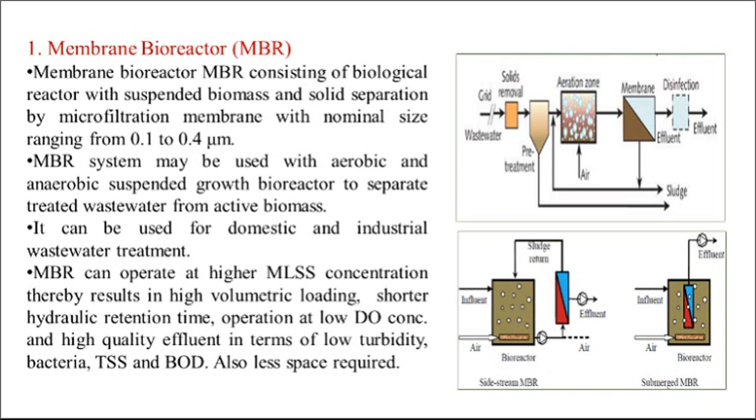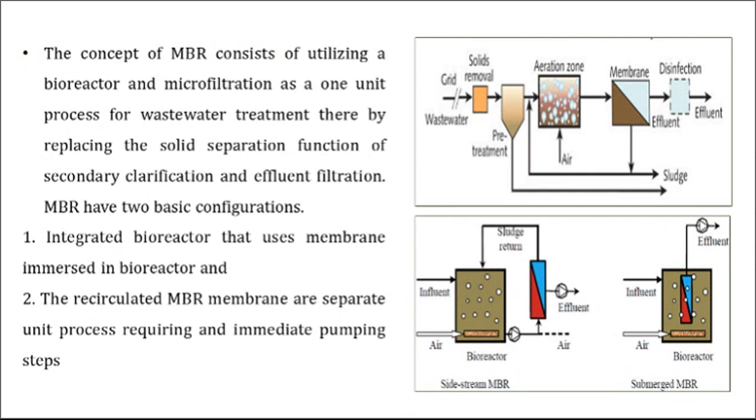Next one, the concept of membrane bioreactor consists of utilizing a bioreactor and microfiltration as one unit process for wastewater treatment, thereby replacing the solid separation function of a secondary clarifier and effluent filtration. It means we are eliminating the secondary filtration unit. Directly a membrane filter is used, and due to that there is no necessity of an SST, secondary sedimentation tank.